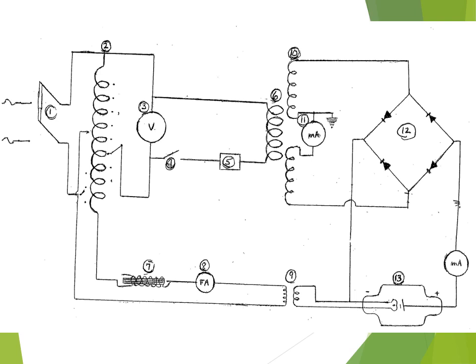So looking at the individual parts that we just talked about, the first one is the main breaker, as we just talked about, and the on-off switch. It's going to include fuses or circuit breakers at the beginning of the whole thing. Number two is the autotransformer, which is going to select voltage, and it also has the line voltage compensator wired to it. Number three is the voltmeter, which is going to read what kilovoltage will be after we produce the X-rays.